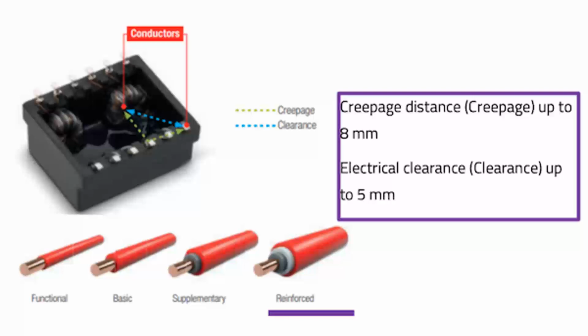The isolation requirement, as well as the normal operating voltage requirement of 250 VRMS, are met with specific design of the electrical spacing. The creepage distance is 8 millimeters and the electrical clearance is 5 millimeters. Furthermore, the transformer windings are created with reinforced insulation.